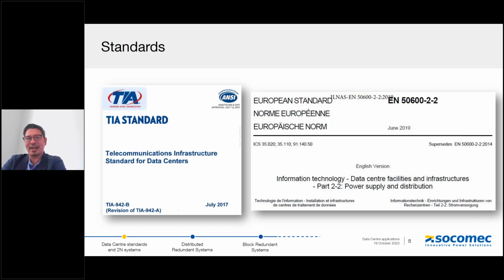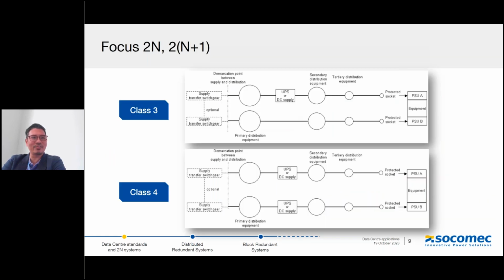Whether it's going to be IT, availability, power, cooling, and network as well. As I mentioned, for today, we're going to focus on two major classifications, which are class 4 and class 3, or tier 3 and tier 4. We focus on these two typical architectures because, as I mentioned, they achieve the redundancy that is required, and also the maintainability, the concurrent maintainability option that we can perform with this architecture.